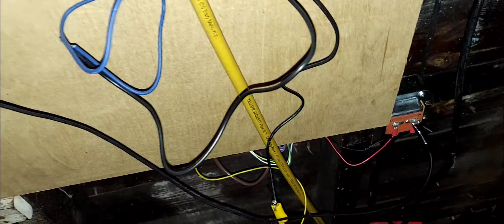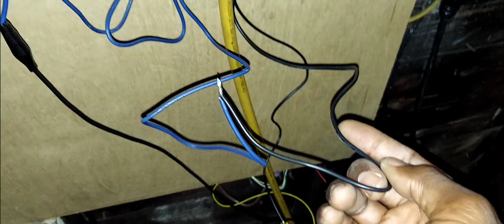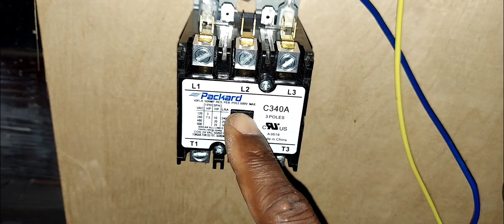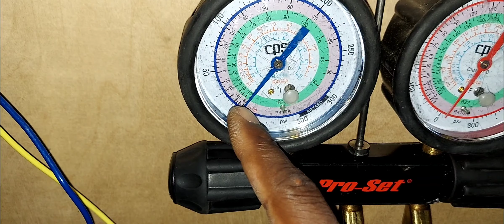And as you can see, real time, I'm going up into my high pressure switch. And then out of my high pressure switch, you see. So the yellow wire is a cooling wire, cooling signal, 24 volts. Goes into my high pressure switch. Out of my high pressure switch, I'm going into my low pressure switch. And out of my low pressure switch, I'm going into my compressor contactor. All right. But my compressor contactor is not on right now because we are below the threshold where my low pressure switch is to be active.